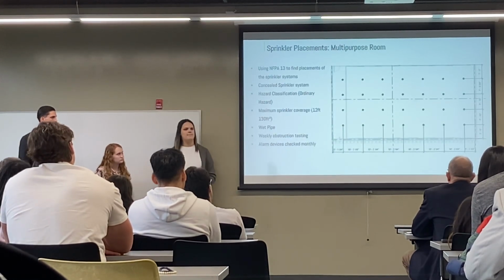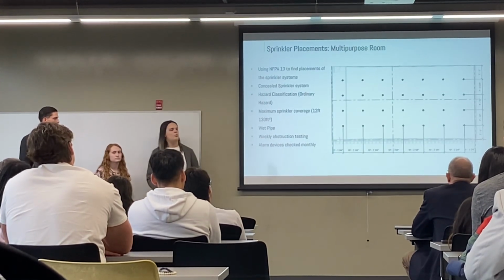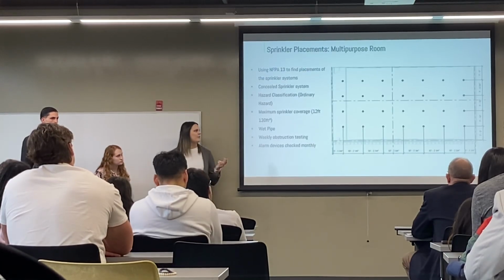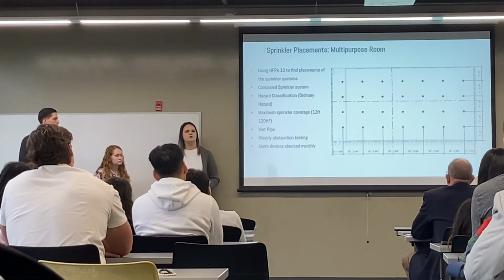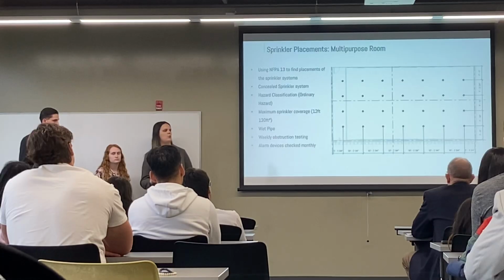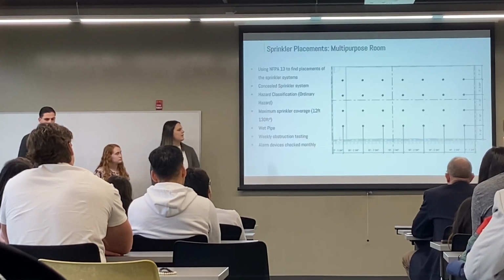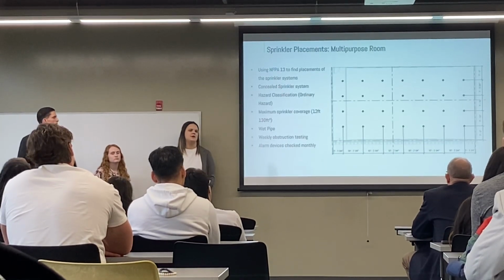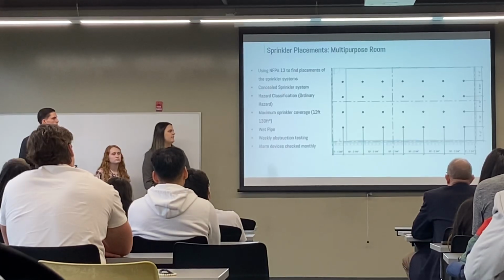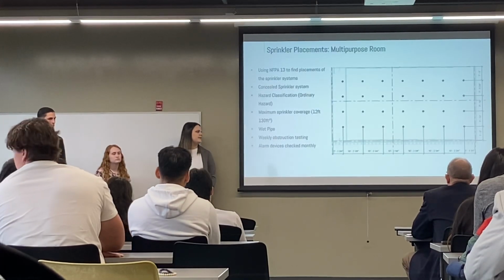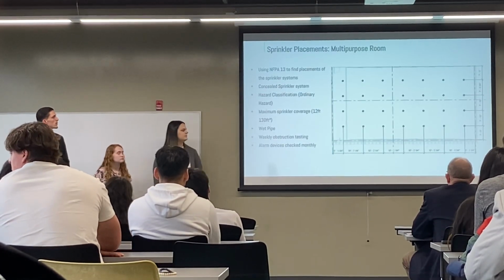And this will be a wet pipe system. So that means when a fire happens, the sprinklers would go off right away instead of waiting for water to come in. Then we have weekly obstruction testing, just making sure that nothing is in the way of those pipes. And alarm devices will be checked monthly.